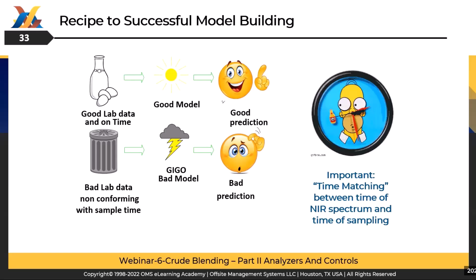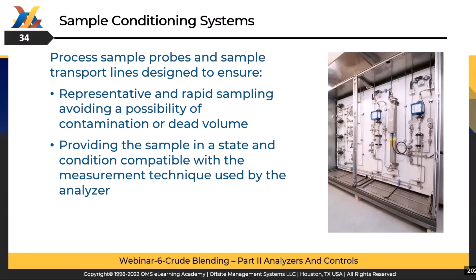Next slide, please. Sample conditioning system. The sample conditioning system is intended to provide a sample in a state and condition compatible with the measurement technique used by the analyzer. Process sample probes and sample transport lines are designed to ensure representative and rapid sampling, avoiding the possibility of contamination or dead volumes. Without representative sampling, results of the analysis won't truly indicate the process condition, and it's impossible to correct these deficiencies with data analytical modeling.